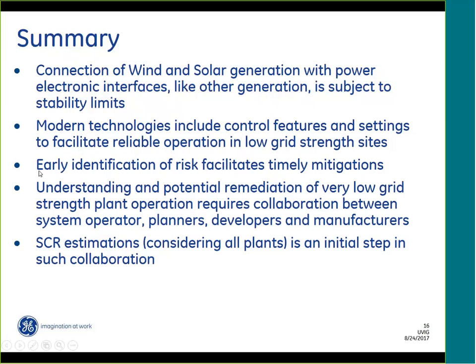Another aspect I will highlight is that the early identification of risks or stability risks in a facility really facilitates timely mitigation. Some of the solutions require quite a bit of time to work out. Even if it's to tune controllers, the systems are so complex that this takes time. If it's to add a synchronous condenser or a STATCOM, that takes time too. Early identification of the potential risk is very useful. To that effect, we talk about the short circuit ratio, basically identifying how weak the grid is.